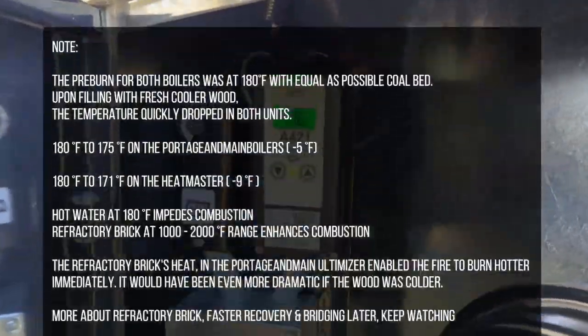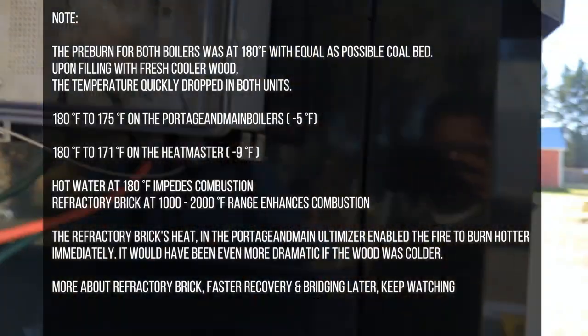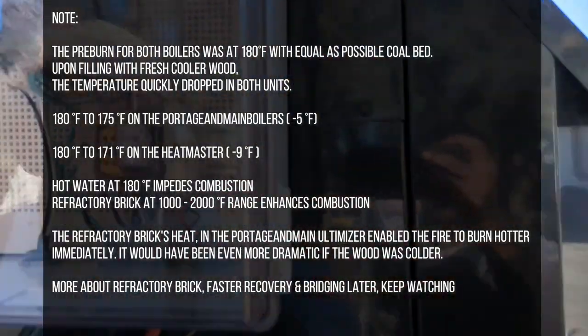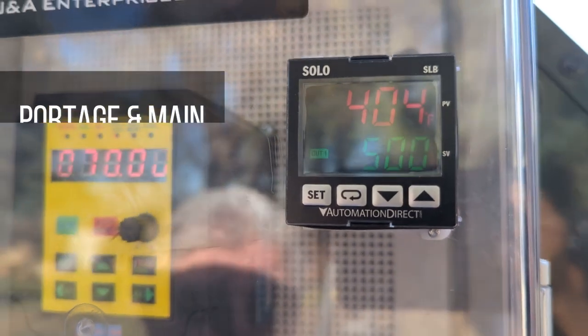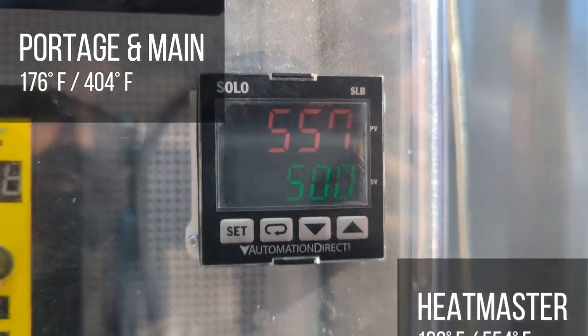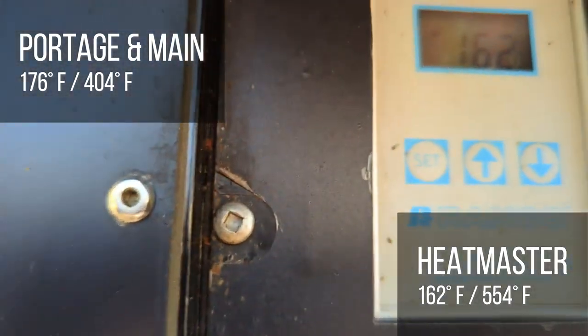The time is 12:50. The Portage & Main is at 176 degrees, gaining temperature. Currently we have two of the 150,000 BTU unit heaters running. The stack temperature on the Heatmaster is at 404 degrees and holding steady, with a water temperature of 546 degrees — wait, the Heatmaster stack is 546 degrees and water temperature is 161, meaning it's falling behind.